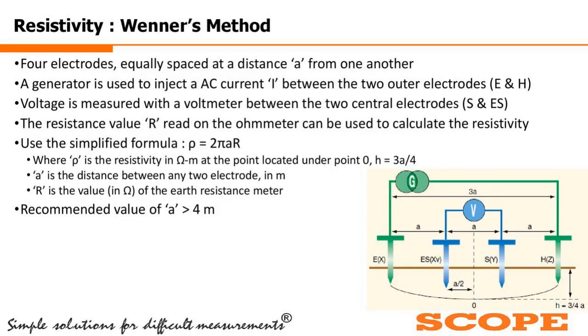Now coming to resistivity measurement through Wenner's method. What is different from the earlier four-wire method? Here also we are using the four-wire method, with four poles or four sticks. In the earlier case we were using the earth electrode as one of the test probes, whereas when we are going for resistivity, we do not have any such earth pit, so we cannot have access to that. So to get the earth resistivity value, we use by default the four-wire, four-stick, or four-pole method.